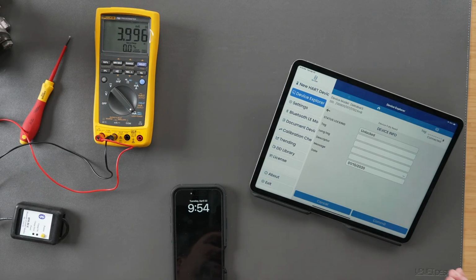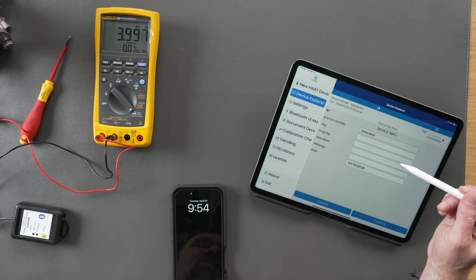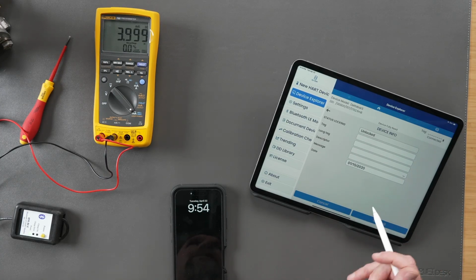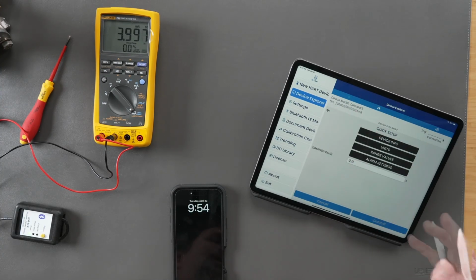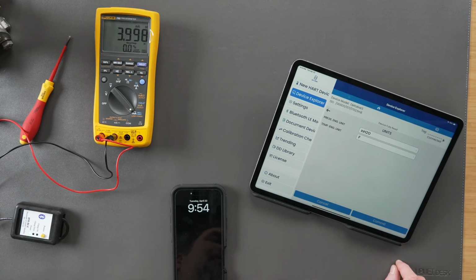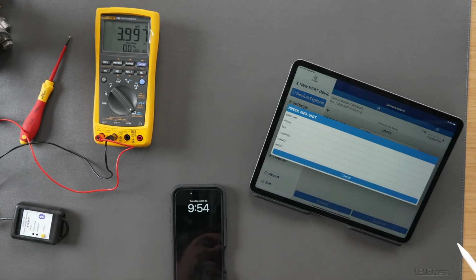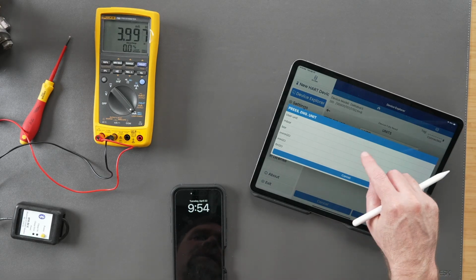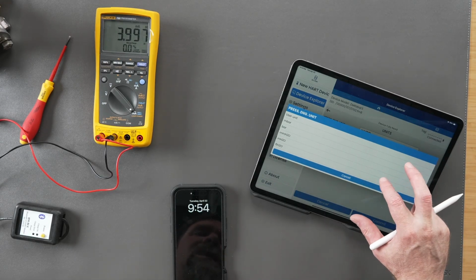In the device info, you can go in there and put the tag, long tag, description, and messages. You can program that short tag and that long tag, and maybe even the description of where this device is within the network. A lot of times that has value. Units of measure, we have to program those. When we did our configuration, we configured ours for pressure units of inches of water column, and it looks like this is the way this one was set up by default.